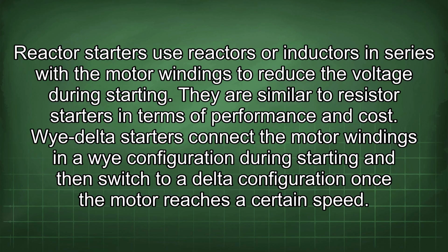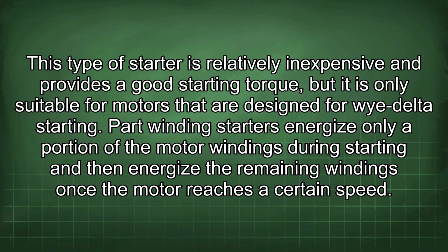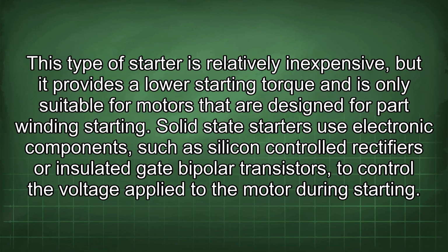Y-delta starters connect the motor windings in a Y configuration during starting and then switch to a delta configuration once the motor reaches a certain speed. This type of starter is relatively inexpensive and provides a good starting torque, but it is only suitable for motors that are designed for Y-delta starting. Part winding starters energize only a portion of the motor windings during starting and then energize the remaining windings once the motor reaches a certain speed. This type of starter is relatively inexpensive, but it provides a lower starting torque and is only suitable for motors that are designed for part winding starting.